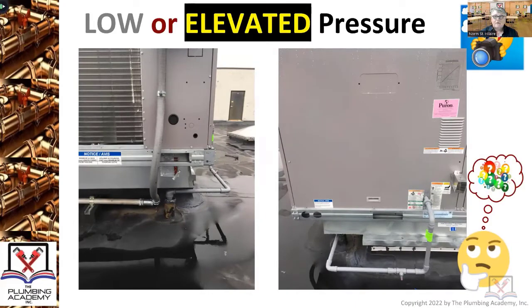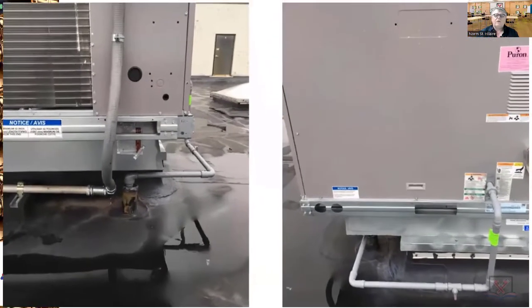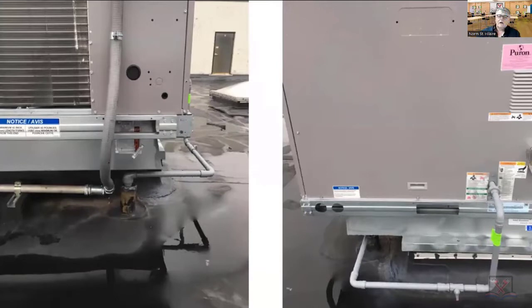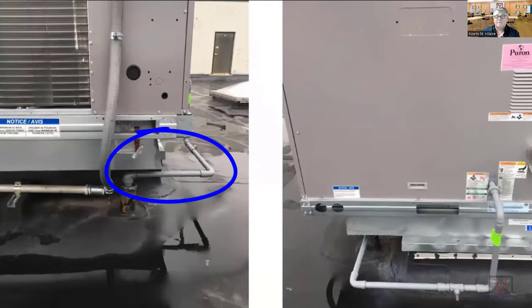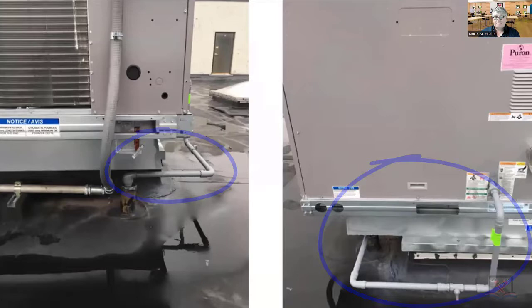You're looking at low or elevated pressure. How many of you think it's low pressure? How many of you think it's elevated pressure? All right, a couple things right off the bat: the pipe's painted gray. If it was elevated pressure, the pipe would be painted yellow. Another point: no regulators anywhere.